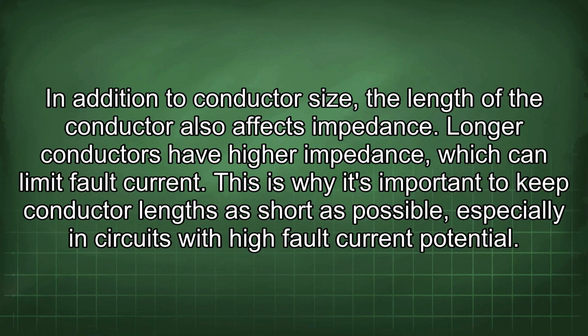In addition to conductor size, the length of the conductor also affects impedance. Longer conductors have higher impedance, which can limit fault current. This is why it's important to keep conductor lengths as short as possible, especially in circuits with high fault current potential.